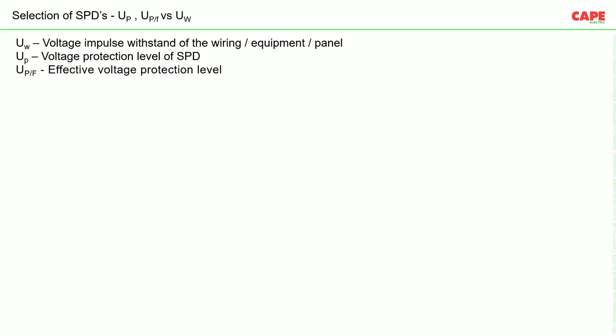Second thing is UP. UP is the voltage protection level of an SPD. That means it is the level at which the SPD starts operating. UP can also be considered as the voltage drop across the SPD. Third parameter is UPF, the effective voltage protection level. That means after considering all the voltage drop across the wire, SPD and the other connecting wire, the resultant voltage protection level is called the effective voltage protection level. Now, to ensure equipment safety, the condition we need to fulfill is that UW shall be higher than UPF. That means the impulse withstand voltage of an equipment shall be more than the effective voltage protection level of that SPD. Then only that SPD is going to protect our equipment.